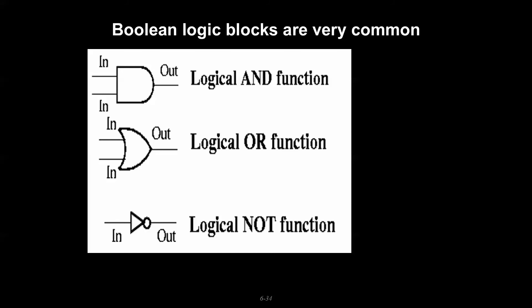We're going to see that these Boolean logic blocks are very common. They deal in zeros and ones. For something like an AND block, we need to have all ones input to this block to be able to pass out a one. You can imagine how that might be helpful where you have something like 'start this piece of equipment if I'm being told to' - that's one input - and the second input may be 'and if I'm not getting alarms.' If those are both one conditions, then you can pass a one out and start some other piece of equipment or send out to some other control loop process.